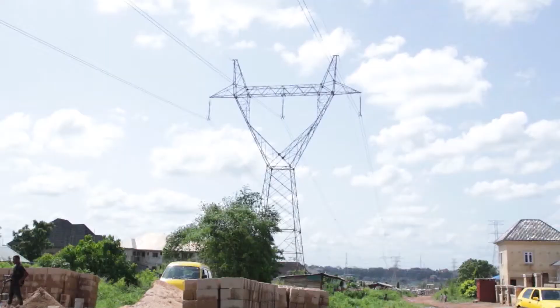The Nigerian Electricity Regulatory Commission, NERC, the power sector regulator, stipulates that for a 330 kilovolt transmission line, a 50-meter distance split equally must be maintained on both sides before erecting structures. For a 132 kilovolt transmission line, the distance must be 30 meters, split equally on both sides.